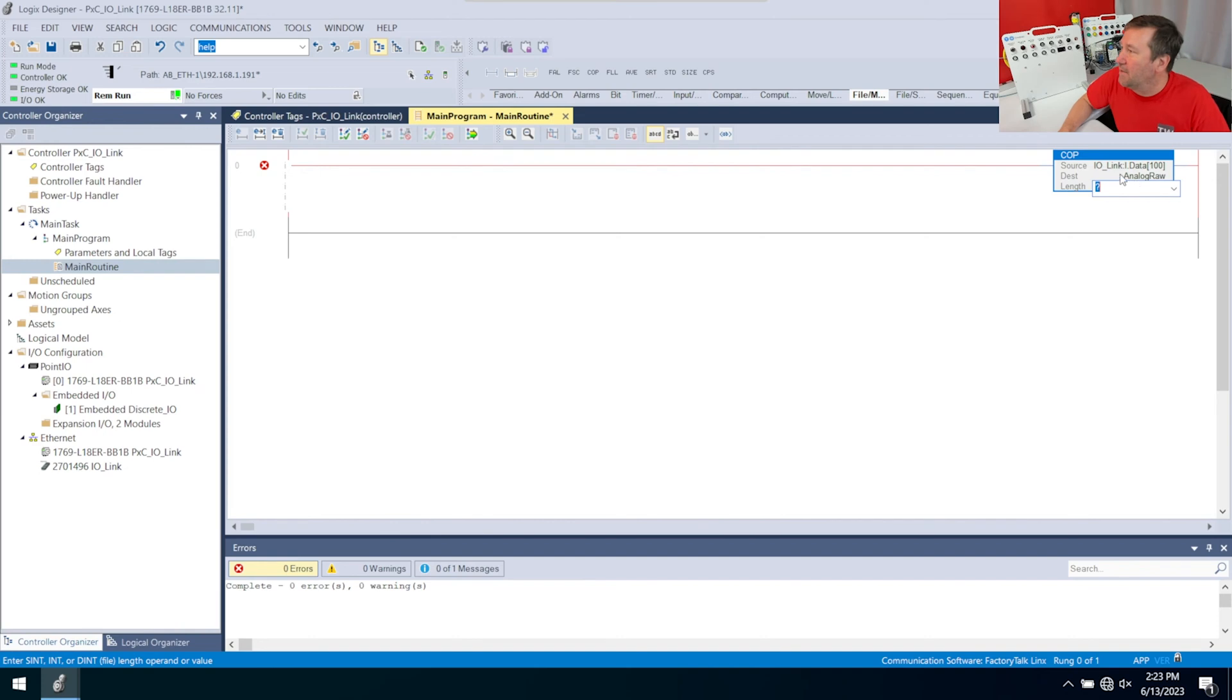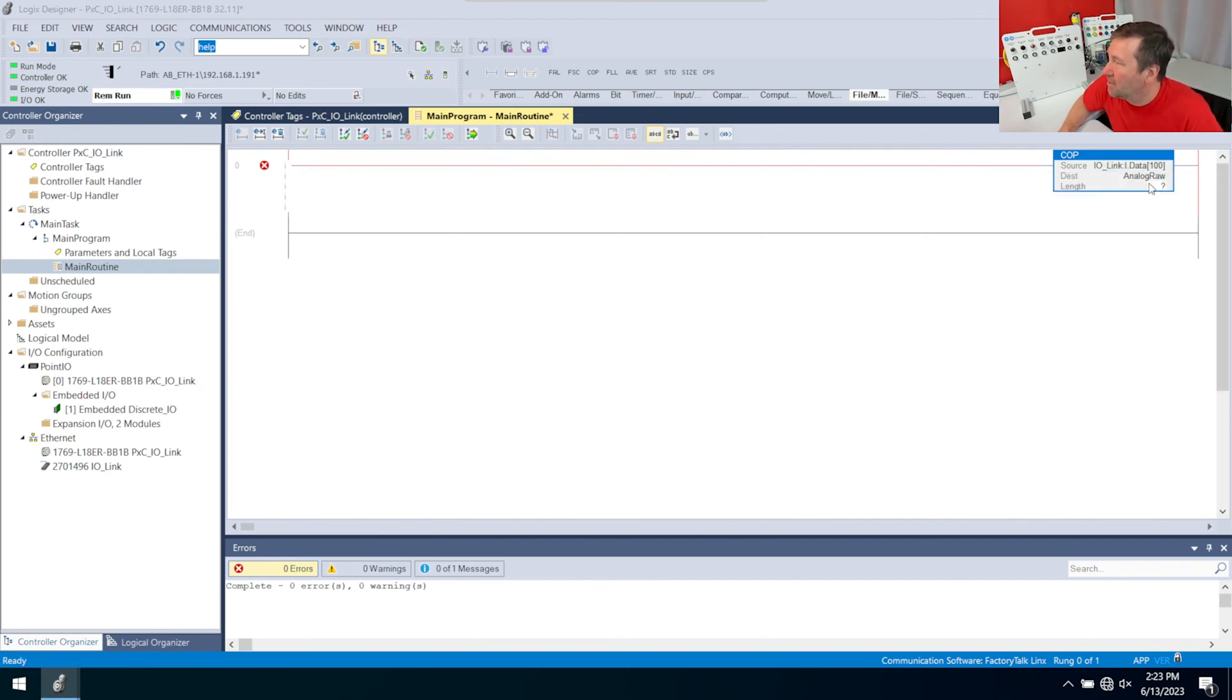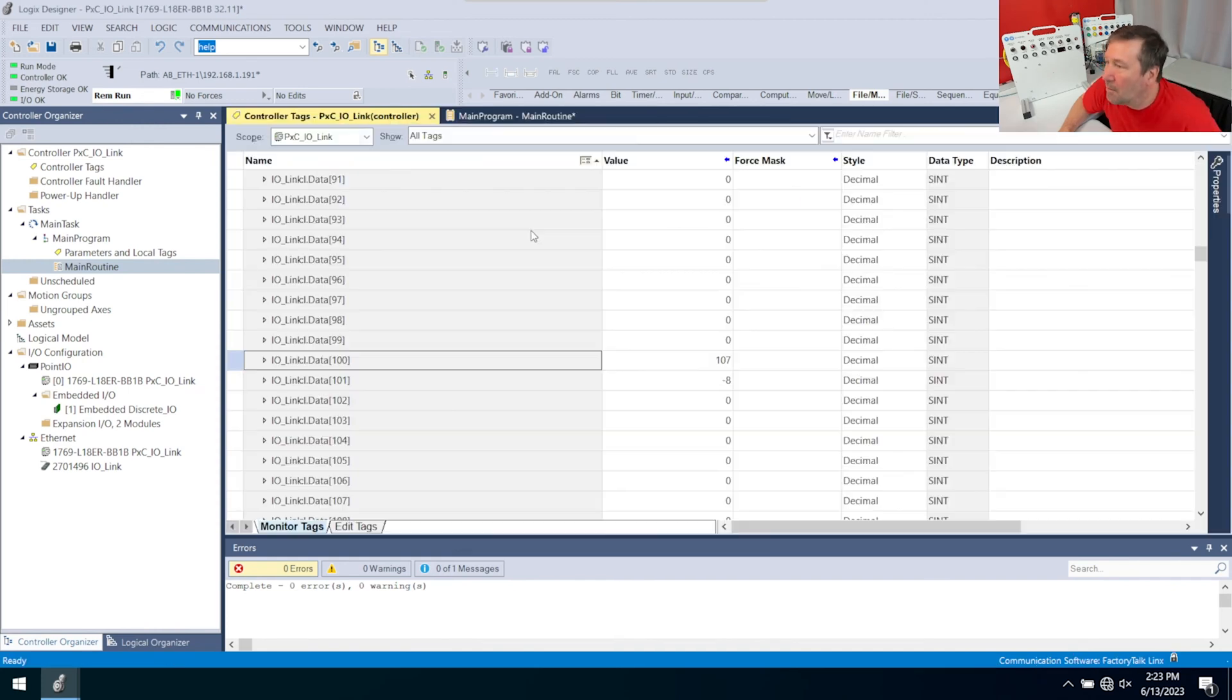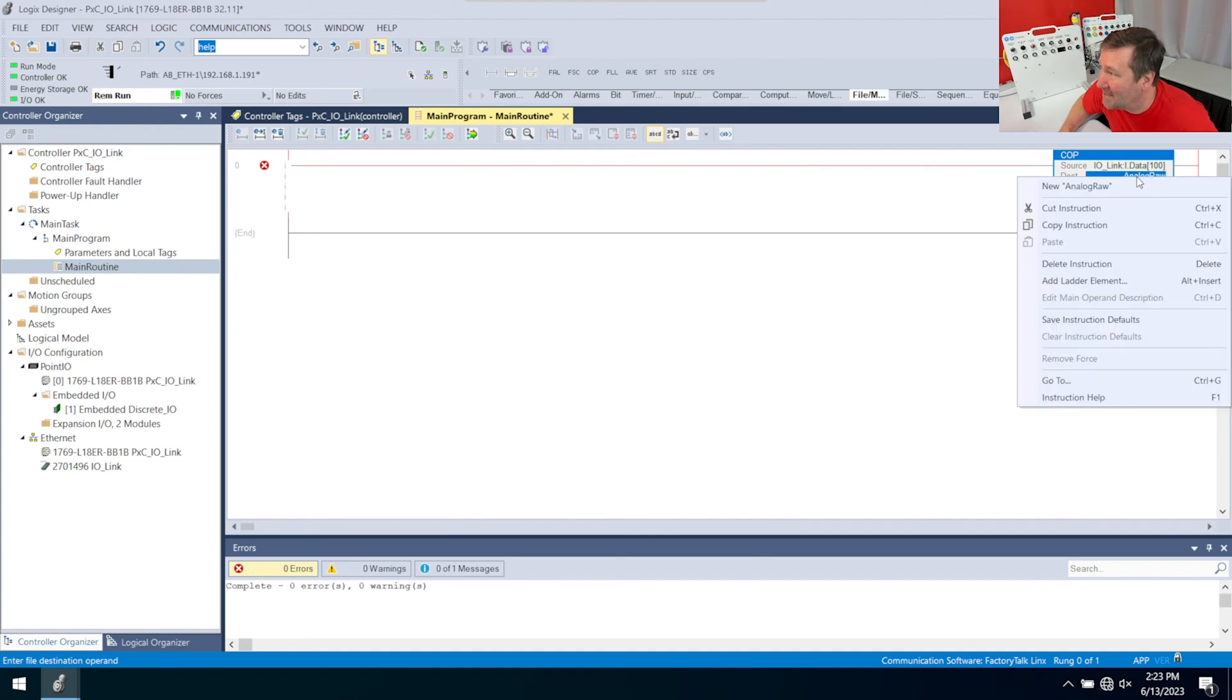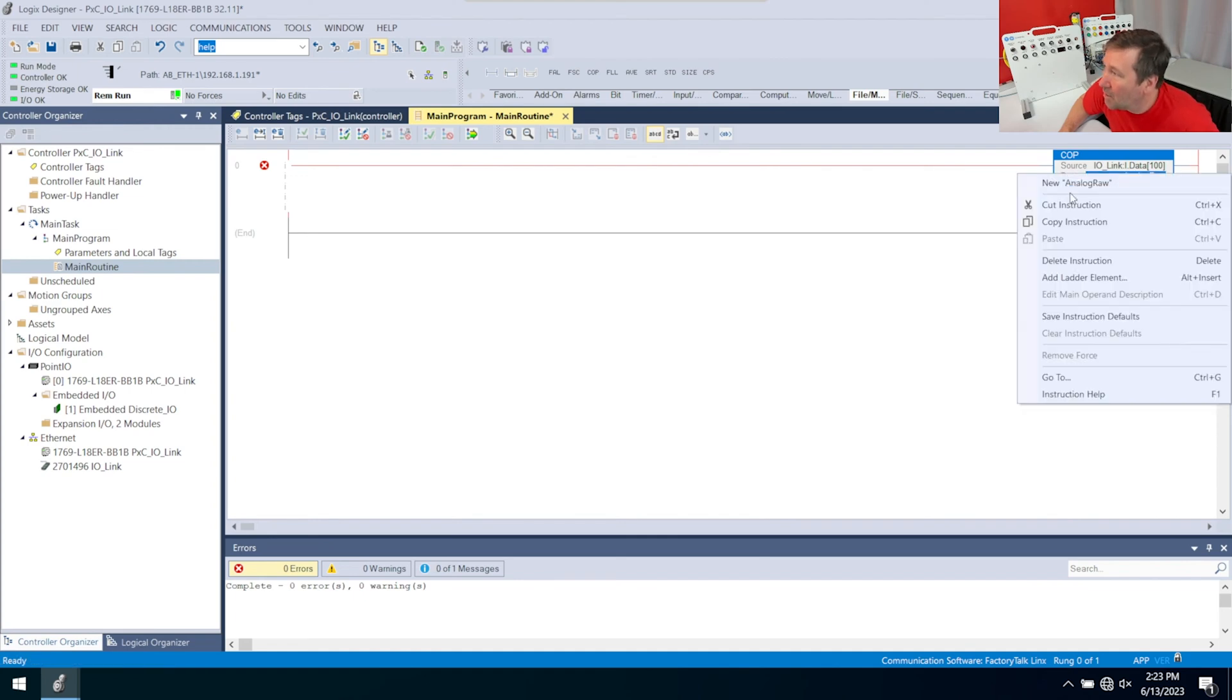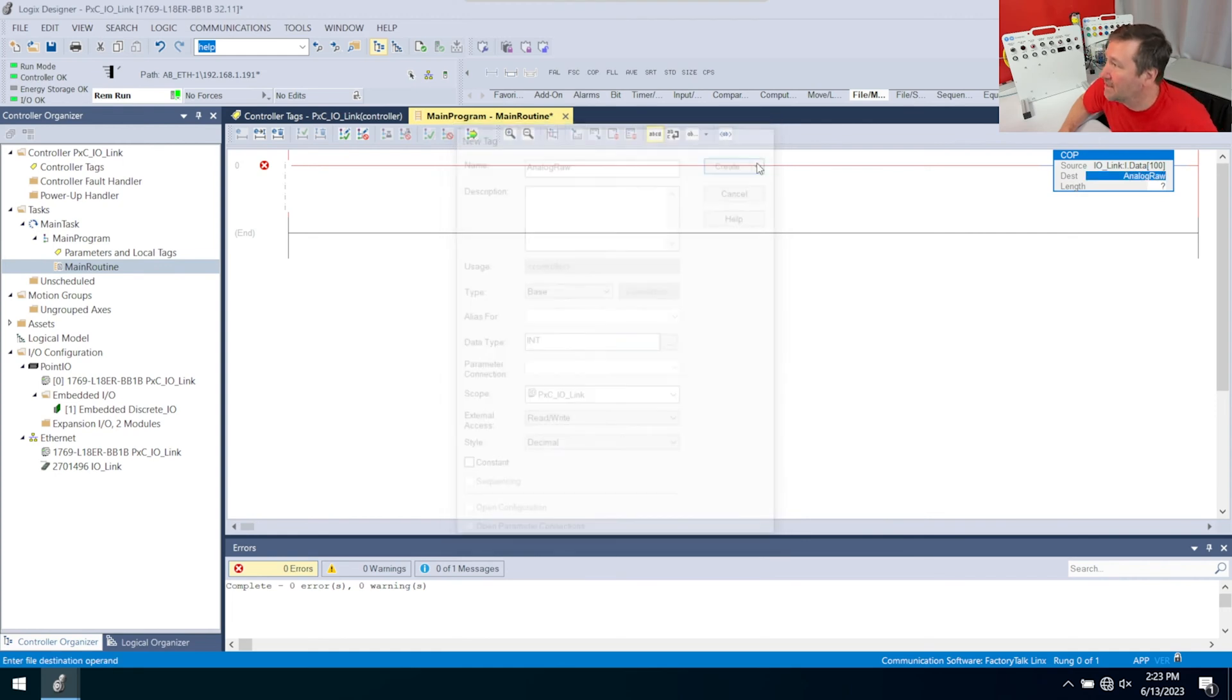The trick is to figure out what data type AnalogRaw should be, because if we just create it, it's going to come up as a double integer, and that's going to be a 32-bit number. But if we look here, this is a small integer, or an 8-bit number. So if we're going to combine two of those, we only need 16 bits, and that's simply an INT. Right-click AnalogRaw, new, and on that data type, change that to an INT and hit create.